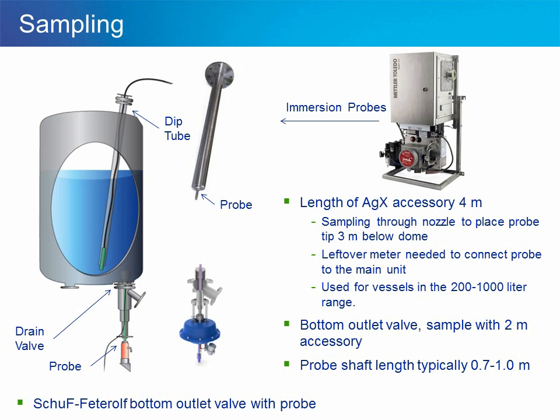The overall length of the silver halide accessory is limited to about 4 meters. Therefore, sampling through a nozzle at the top of the vessel will allow the probe tip to be placed about 3 meters below the dome, with a leftover meter needed to connect the probe to the main unit. This approach is often used for vessels in the 200 to 1,000 liter range. By going through a bottom outlet valve, a vessel this size can be sampled with a 2 meter accessory. The probe shaft is designed to match the valve, and the length of the shaft is typically 0.7 to 1 meter.